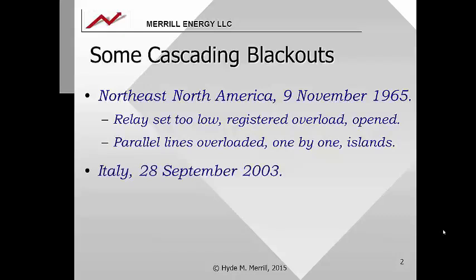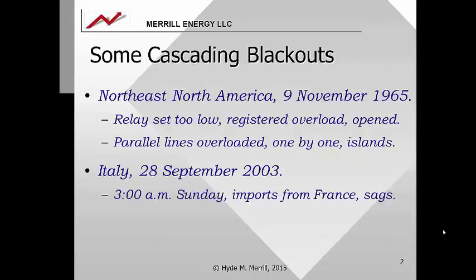Early Sunday morning, on the 28th of September 2003, Italy was importing a large block of power from France—actually 300 megawatts more than it had contracted to import. As a result, lines got warm, expanded, and sagged. At one minute after 3 o'clock in the morning, one line sagged so far it came in contact with a tree. The short circuit caused the line to be taken out of service.